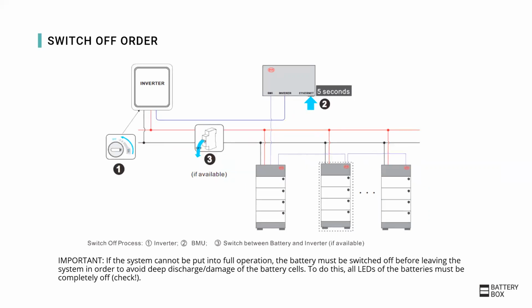For switching off the system, it is exactly the other way around than switching on. First the inverter, then the battery. To switch off the battery, the LED button on the BMU should be pressed for 5 seconds. Then all LVS modules should turn off.